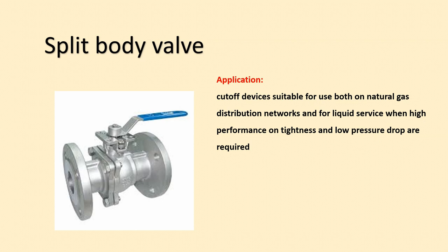Next is the split type valve body. It is not widely used; it is mainly used in gas industries because it is a cut-off device suitable for natural gas distribution networks and for liquid service when high performance on tightness and low pressure drop are required. This valve body offers tight shut-off while also providing very low pressure drop, so it finds its applications there, and is not widely used in process industries apart from gas industries.